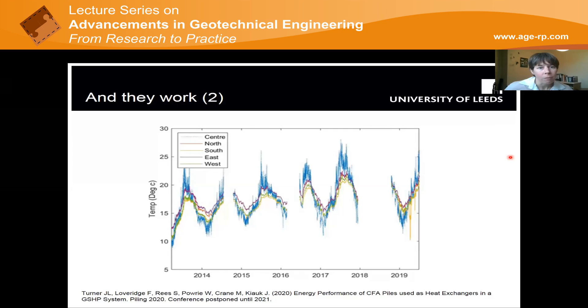Okay, so moving on to thermal behaviour. You're probably starting to see why thermal behaviour is potentially important, but essentially what we're interested in knowing is how much energy we can get out of the ground, while maintaining a reasonable range of temperatures that won't affect the primary structural function of the piles or the safe operation of the heat pump. We want to maximize the energy for the length of pile we're going to construct anyway for our building, within specified temperature limits. We don't want to freeze the ground, we don't want to heat the pile so much that the temperature changes affect geotechnical performance, and we also don't want it too hot because that affects the efficiency of the heat pump system.